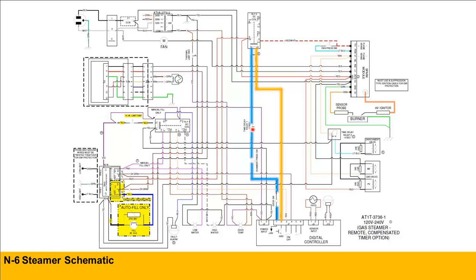So easy enough. We can test across, or for me, hey, just go ahead and jump it. Let's see if it works, and then we'll go ahead and bypass that switch and see if that relay pulls in and see if it starts calling for heat. So once again, we jumped it, and nope, still no call for heat.